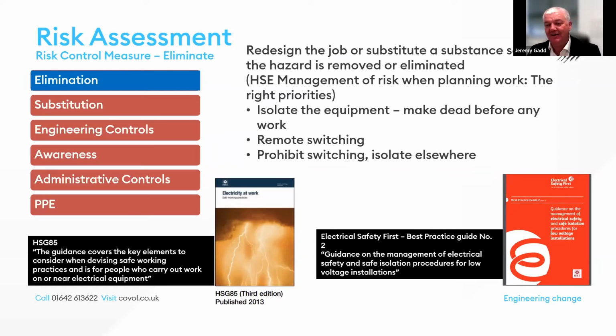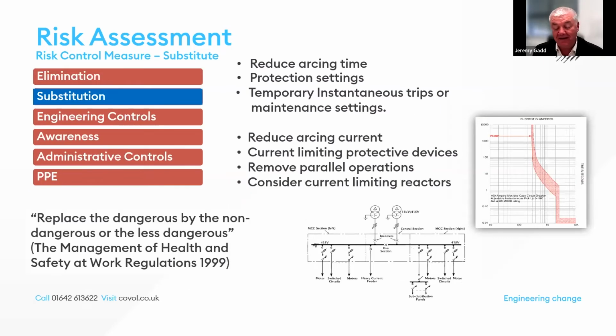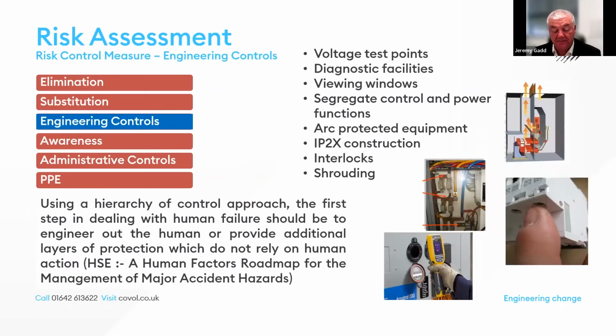The next one is substitution. If you recall from a few slides back, reducing the time or the current will reduce the incident energy levels, and adjustment of protection settings will go some way in achieving this. Next up is engineering controls. And this may prove difficult to achieve given that equipment is already installed and in use, although there are some points on here that may prove beneficial to some.